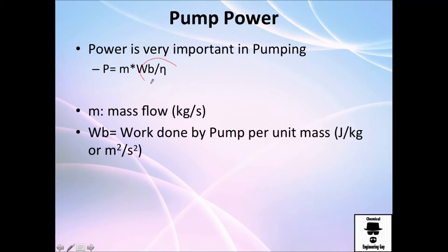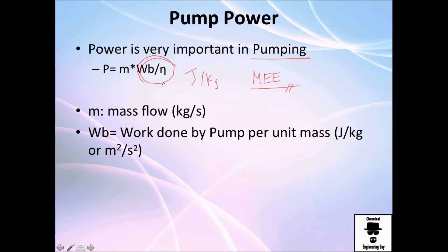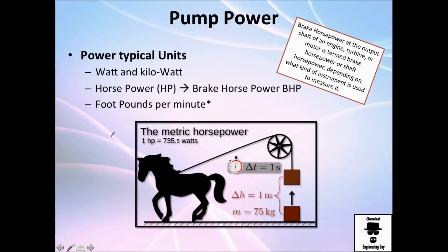To get the pump power, you need to know the head of the pumping requirements — that is, how many joules per kilogram — obtained from the mechanical energy equation. You also need the efficiency and the mass flow. Typical power units are the watt or kilowatt, which are joules per second or kilojoules per second.